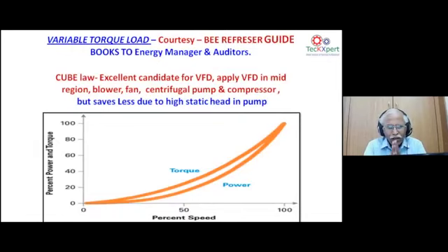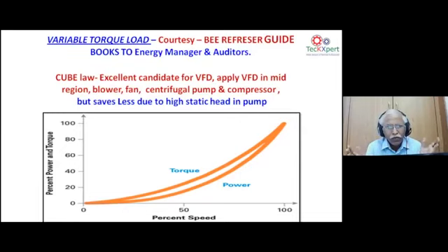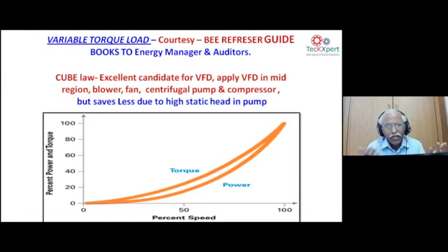Acknowledging the Bureau of Energy Efficiency's refresher guide and course materials for energy managers and auditors — excellent content that we've been able to revisit during COVID time. We follow the cube law, which is an excellent principle for variable torque loads. Industries have two types: constant torque loads (productive machines, ~8 out of 10) and variable torque loads (utilities — centrifugal compressors, pumps, blowers, fans). The difference between a fan and blower is only in the pressure: below ~1000 pascals is called a fan; above ~2000 pascals is a blower.